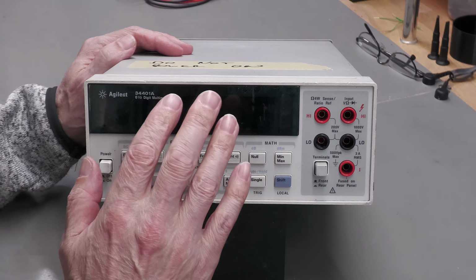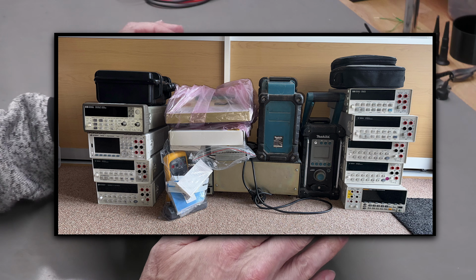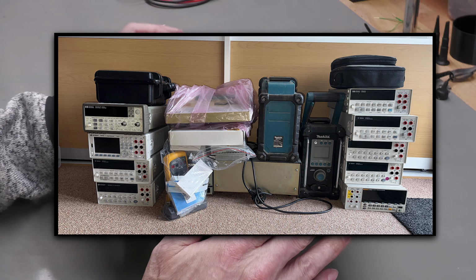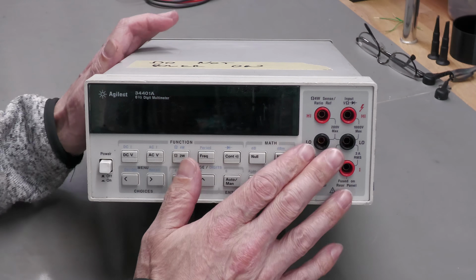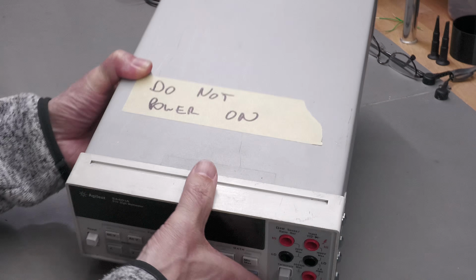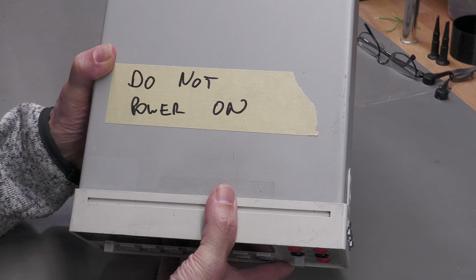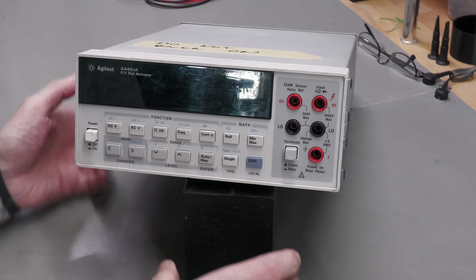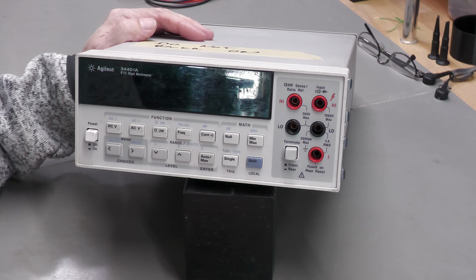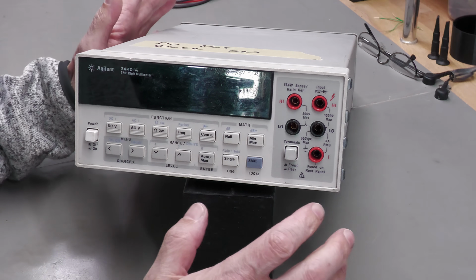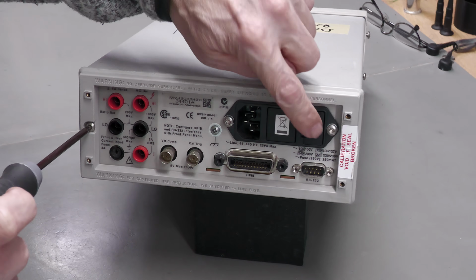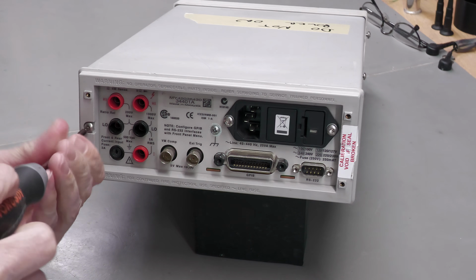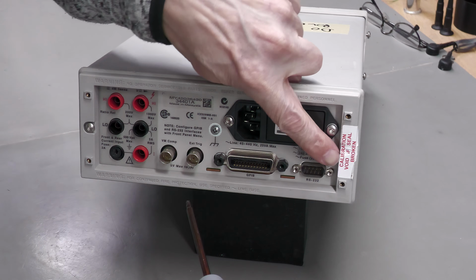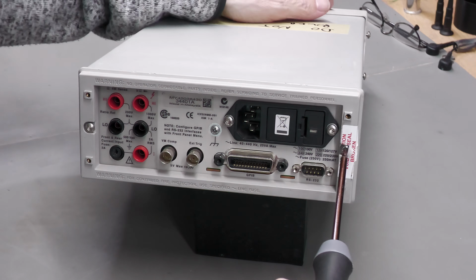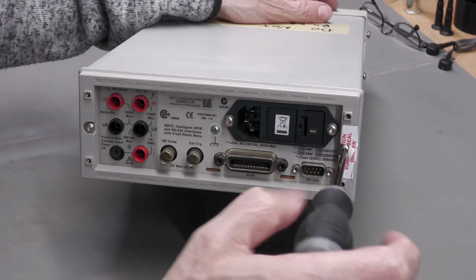And this time I've got an Agilent 34401A 6.5 digit multimeter. I'll put a photograph on screen. This is part of a collection of test instruments and other electronic items I've got to check over for a friend. Some of it we know is faulty. This particular unit I know nothing about, apart from the fact it's got this on top: do not power on. But why that is, I've got no idea. Worst case scenario, the insides are all burnt out or there's a dead short across the circuit board. The only way to find out is to open it up. I've had a quick look at the fuse, and it's actually intact, and the supply is selected for 240 volts. I noticed the calibration sticker is intact over this screw, so at least it looks like nobody's been inside it. Well, it looks like that anyway, but you never know.